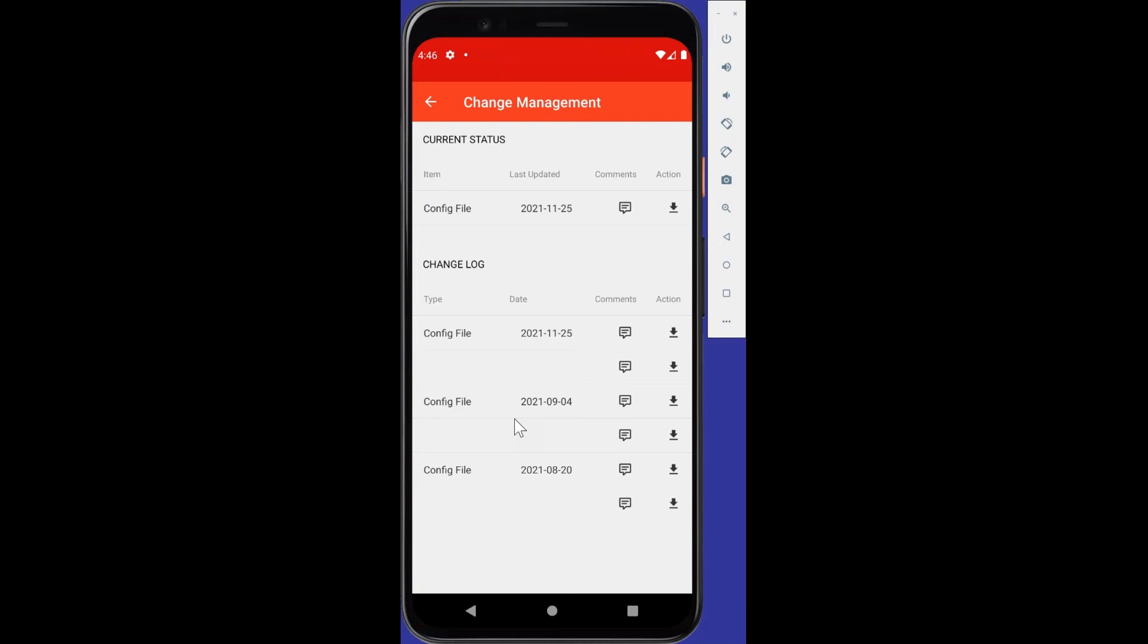I can go ahead and hit download. That file will physically be on my mobile phone. And then when I'm at that site, I can connect to that pump and upload the file by connecting to the onboard web server or simply entering the details or the parameters for those configuration parameters that might have been changed. So a really, really handy tool, particularly when it comes to managing the asset or change management, as we refer to it more generally. Let's back out.